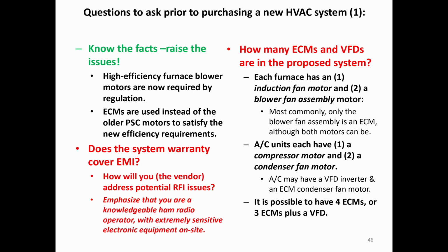A really key question is, how many ECMs and or VFDs are in the proposed system? Nowadays, modern systems can have 3 ECMs, one for the condenser fan, one for the blower fan, the furnace, one for the draft inducer fan, the furnace, and finally either a VFD or possibly an ECM. They both have the same problem. In the air conditioner, I know Lennox field techs have told me they run into this, particularly in commercial systems.